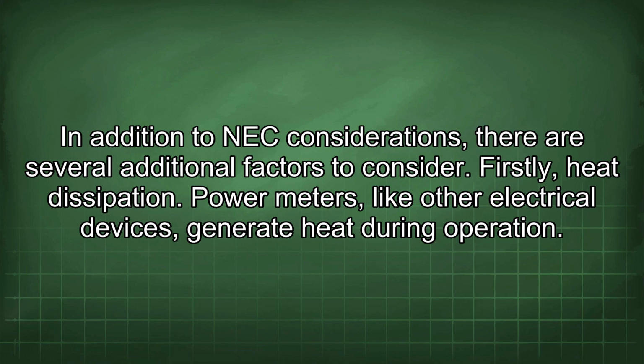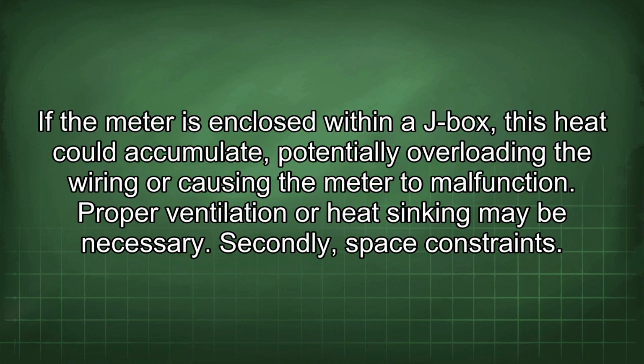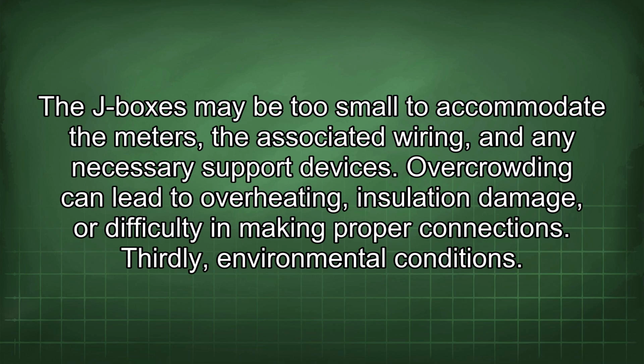Firstly, heat dissipation. Power meters, like other electrical devices, generate heat during operation. If the meter is enclosed within a J-box, this heat could accumulate, potentially overloading the wiring or causing the meter to malfunction. Proper ventilation or heat sinking may be necessary. Secondly, space constraints. The J-boxes may be too small to accommodate the meters, the associated wiring, and any necessary support devices. Overcrowding can lead to overheating, insulation damage, or difficulty in making proper connections.